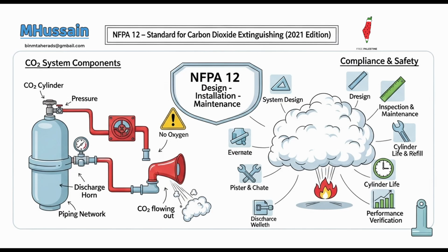Specific wording, okay. Like what? For example, a sign in every protected space reads, "Warning, carbon dioxide gas can cause injury or death. When alarm operates, vacate immediately." Clear and direct. At every entrance to a protected space, it's, "Warning, carbon dioxide gas can cause injury or death. When alarm operates, do not enter until ventilated." Don't go in. Wait for ventilation. And at a manual actuation station, it reads, "Warning, carbon dioxide gas can cause injury or death. Actuation of this device causes carbon dioxide to discharge. Before actuating, be sure personnel are clear of the area." Warning before you pull the handle.